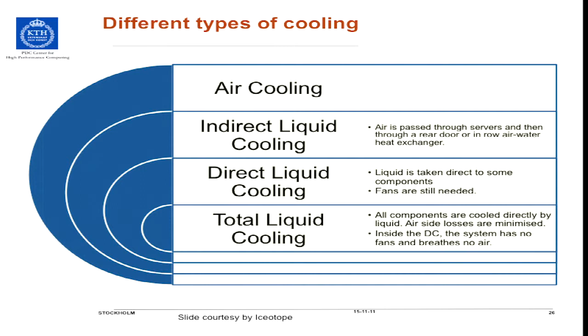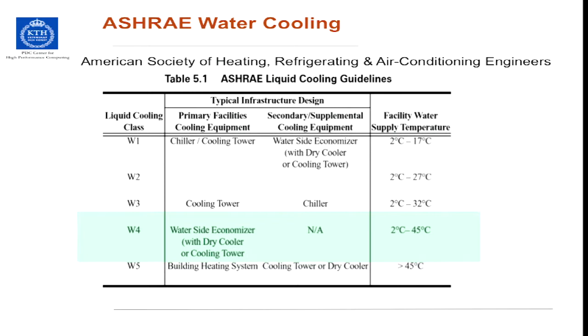A problem with liquid cooling is that there are many kinds of water requirements — each system has its own, which is a problem. There's an organization in the US called ASHRAE which tries to classify water into different categories, with different temperatures for different applications. But not everyone follows this, and each computer system today has its own characteristics for cooling, pressure, temperature, and the cleanness of the water required. So that's one of the problems.